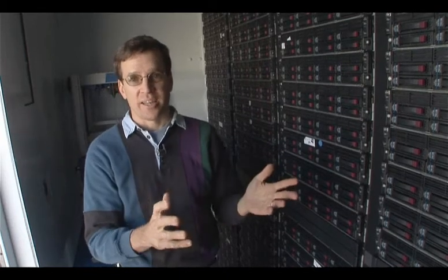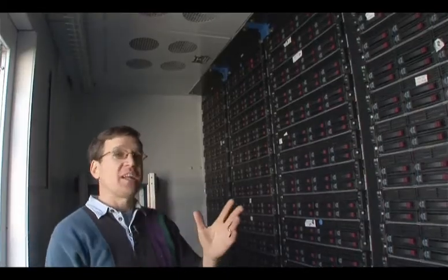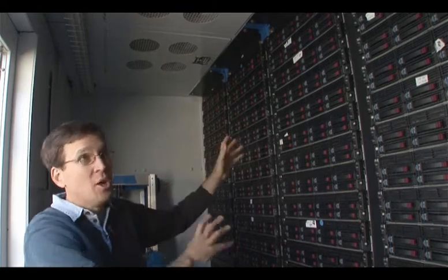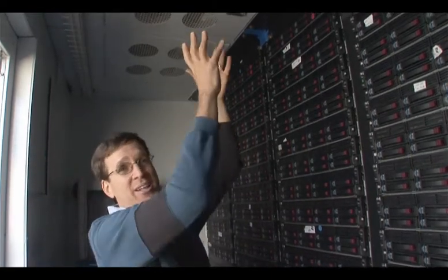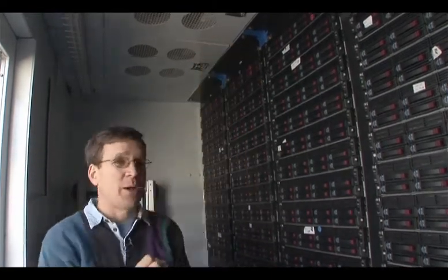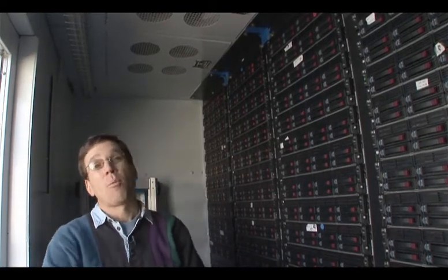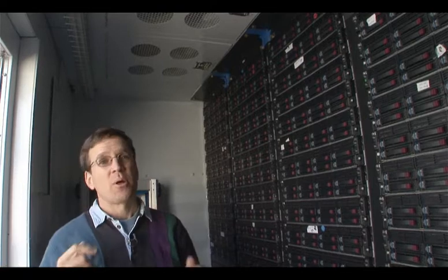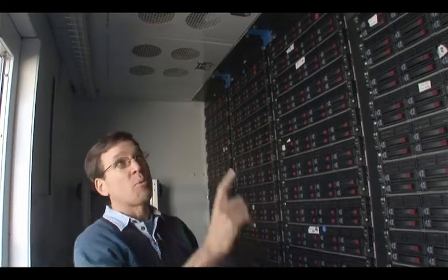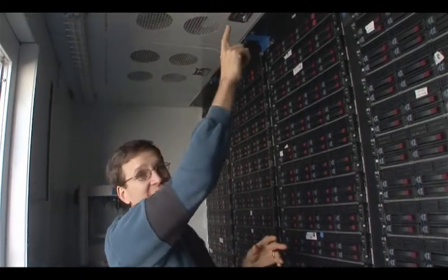On the cooling side, one of the reasons we're more efficient is instead of having the computer and air conditioners a long way away, we've actually moved the fans directly in front of the servers. That allows us to use warmer air and warmer water from the facility level, but it also allows us to use lower blower power to move that air in the data center.